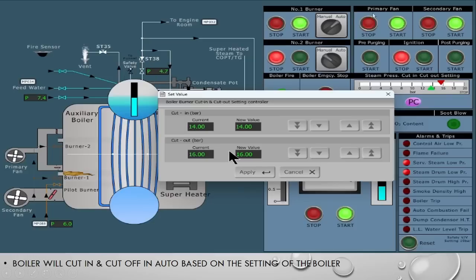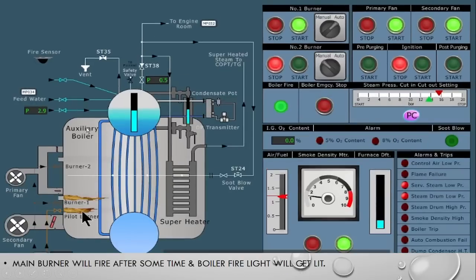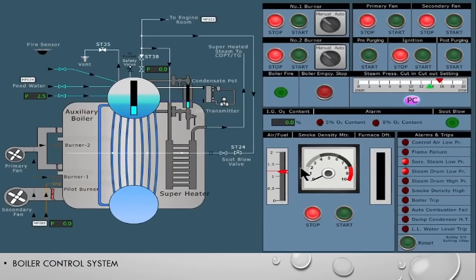In auto mode, the cut-in and cut-off set values are configured. For example, the boiler will cut in when the pressure drops to 14 bar and cut off when the pressure rises to 16 bar. This limit is not fixed for every boiler — it depends and differs. If it is a low-pressure boiler operating in the range of 6 to 9 bar, maybe the cut-in is 6.5 bar and the cut-off is 7.9 bar. You have to see your own boiler settings to know at what pressure the cut-in and cut-off are set.